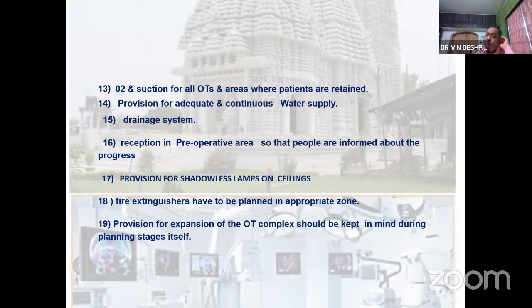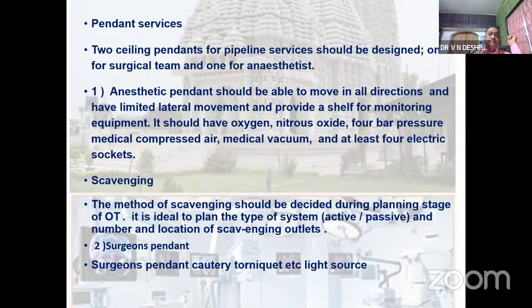If you are going to use bore water, use water softeners and do not waste time in adding it, because it chokes up your taps and drainage systems. Then drainage systems are to be wide. They have to be non-blocking. The reception outside the OT is also a very important asset because that keeps relatives informed about what's going on inside. Provision for shadowless lamps on ceilings, fire extinguishers, provisions for expansion of OT complex.